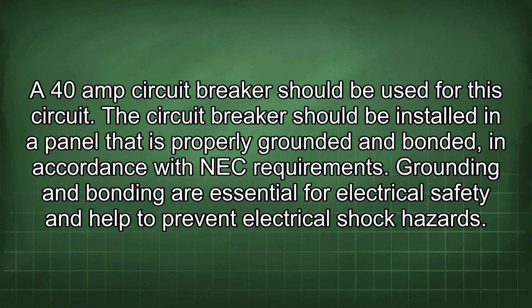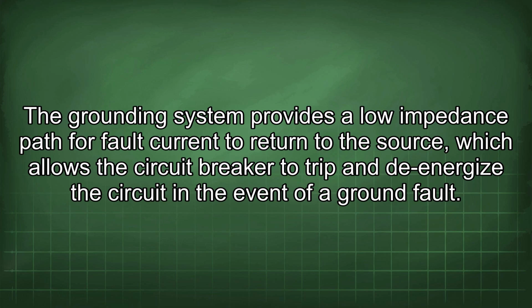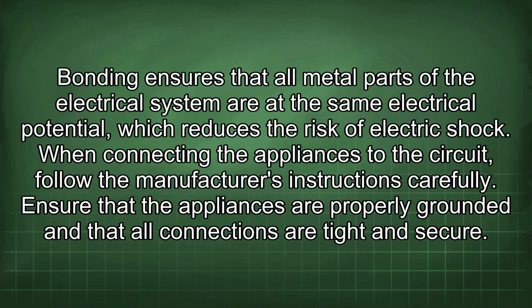The circuit breaker should be installed in a panel that is properly grounded and bonded in accordance with NEC requirements. Grounding and bonding are essential for electrical safety and help to prevent electrical shock hazards. The grounding system provides a low impedance path for fault current to return to the source, which allows the circuit breaker to trip and de-energize the circuit in the event of a ground fault.